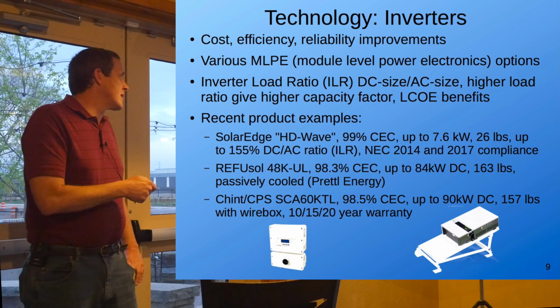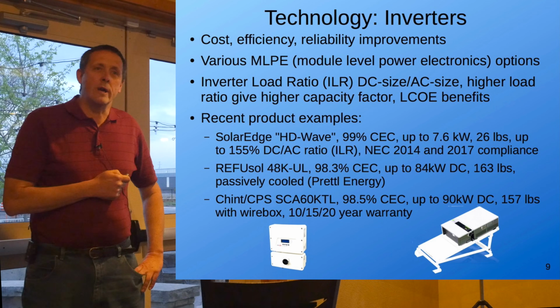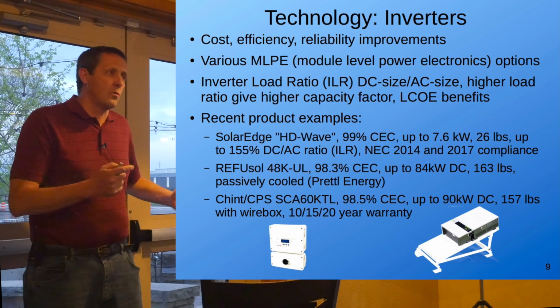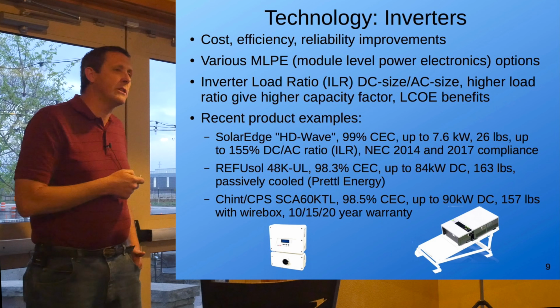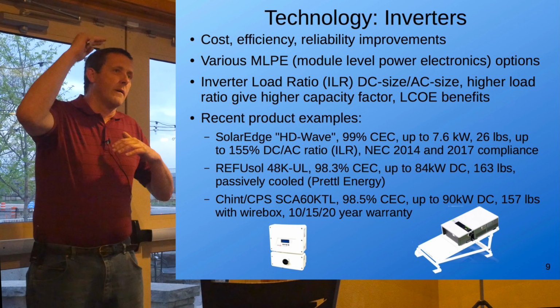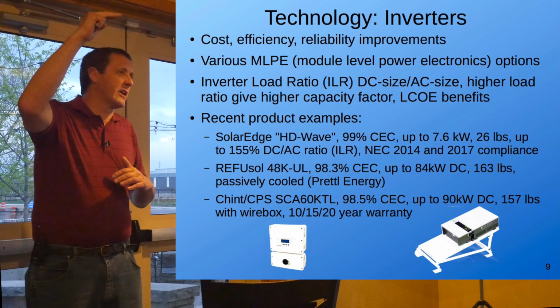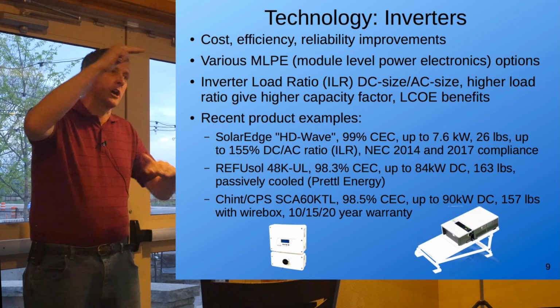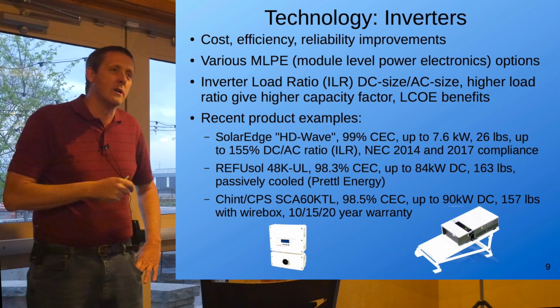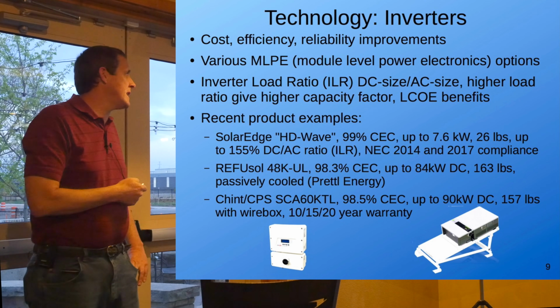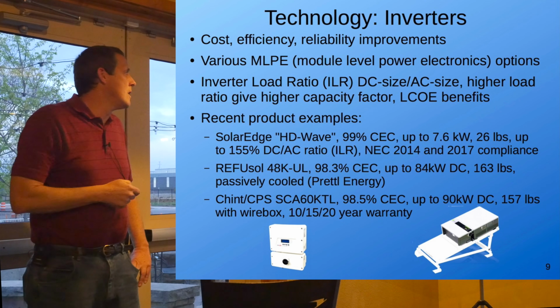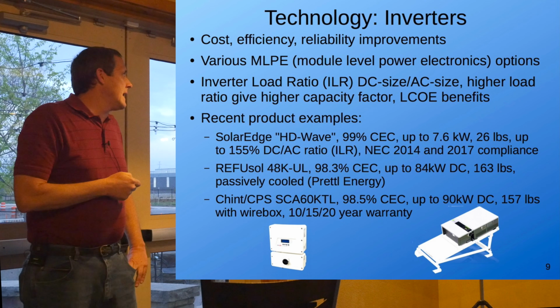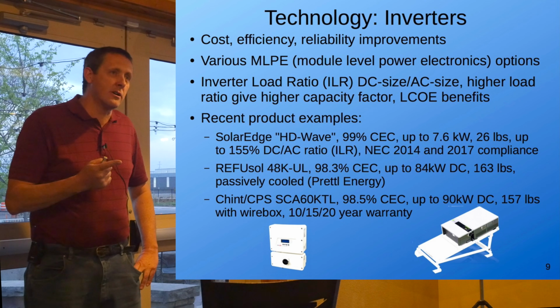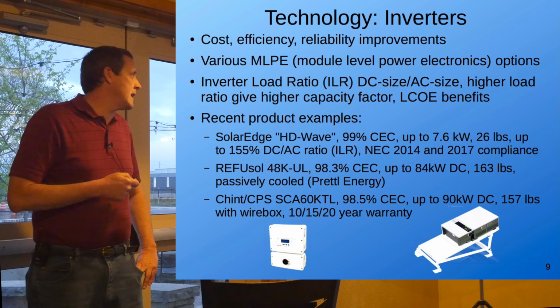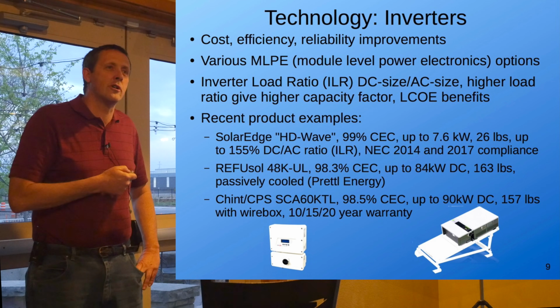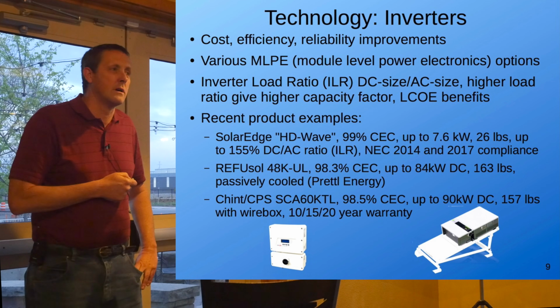Another big factor in inverter design now is the inverter load ratio. We've known for a long time we can exceed the rating, so we can have 120 kilowatts of DC power in just a 100 kilowatt inverter. That's a 1.2 DC to AC ratio. What that helps with is giving you a higher capacity factor, and it also increases the return on investment over a long lifetime.